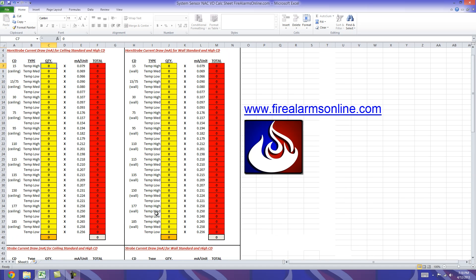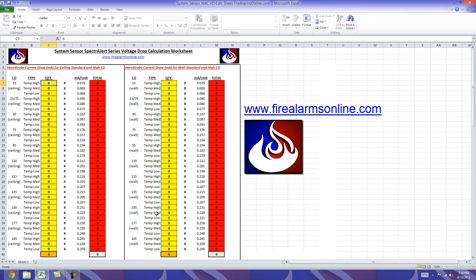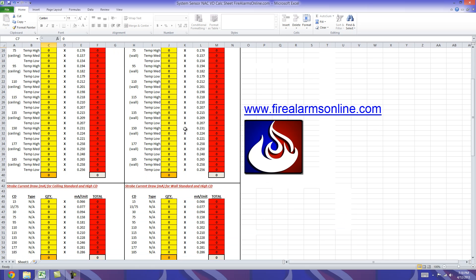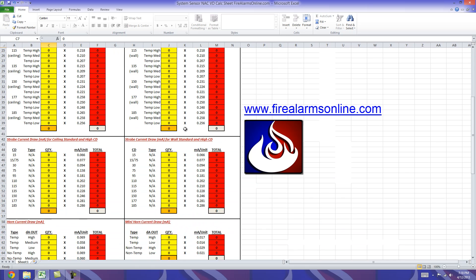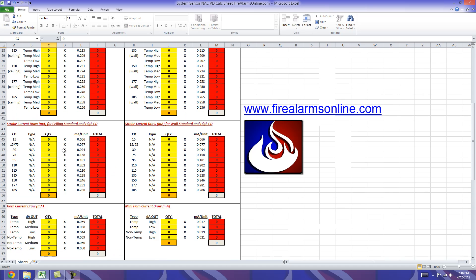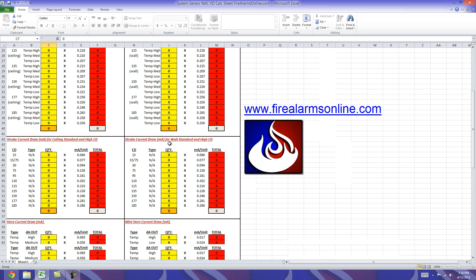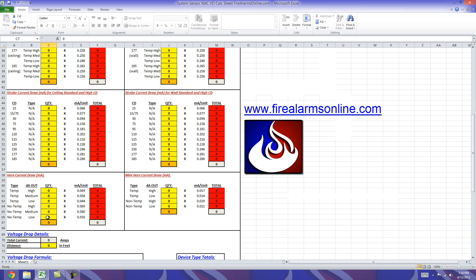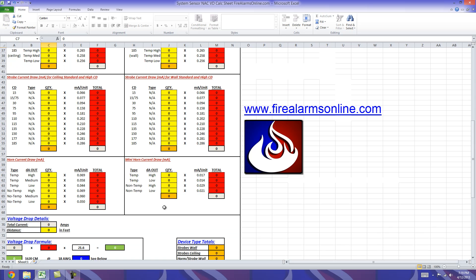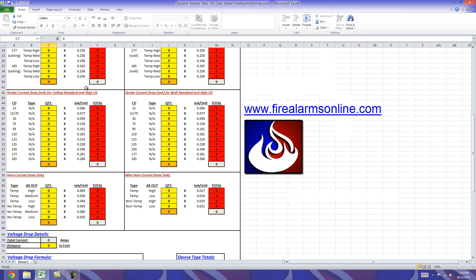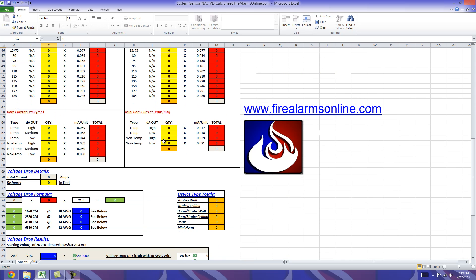Now System Sensor, unlike other manufacturers, they have the same current draw for their wall and ceiling mount devices so this is kind of redundant. But I thought I'd still add it in there because like we discussed down here with the device total section, you'll notice here there's an orange cell at the bottom of each of these quantity rows or columns and that's where you're going to get your totals. So at a very minimum, at least you can put your circuits in your device quantities and you'll still get an account here of all the devices you have for your layout.